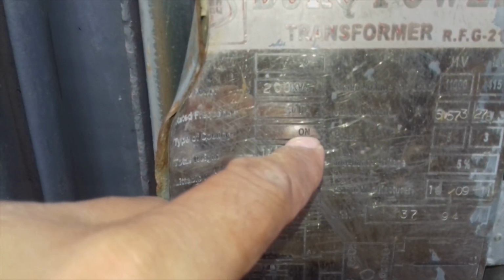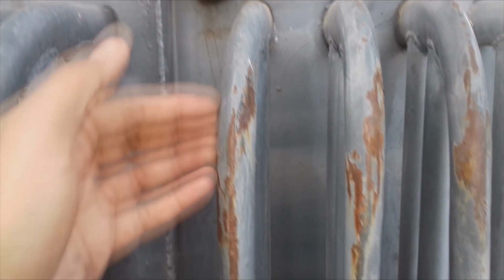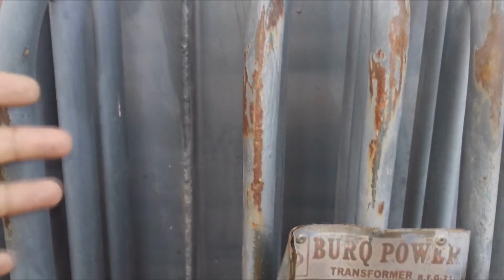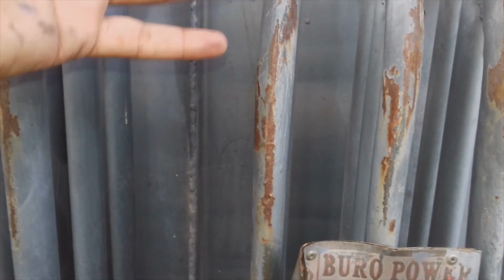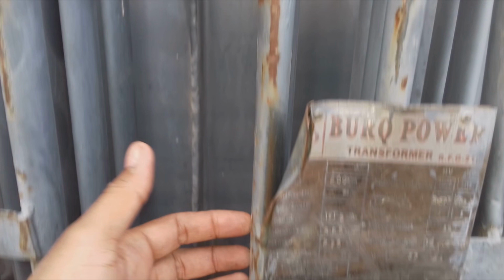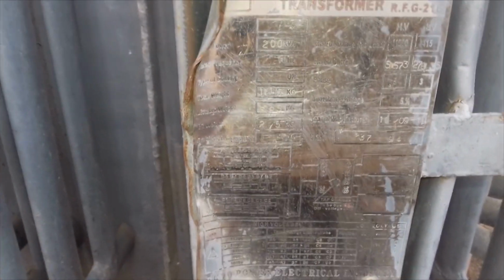So this is the type of cooling, you can see, oil natural. Here these radiator pipes you can see, they are bringing the hot oil from the top to the bottom, and natural air is cooling this radiator, and in turn the oil is cooled and going down, and then from the downside it is entering the transformer tank, and this is occurring all the time.